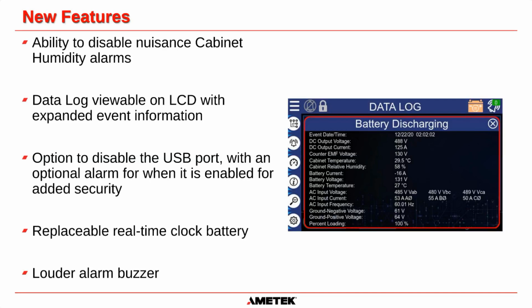We also have a real-time clock on this, so if you don't use network time protocol, you can still set and keep your time and date, and that battery is now replaceable. If the battery voltage starts to go low, you will get an alarm that says the display battery is low, so it can be replaced while the system is running. We also have a new louder alarm buzzer; the old buzzer on the old systems is underpowered and was very hard to hear in loud environments.